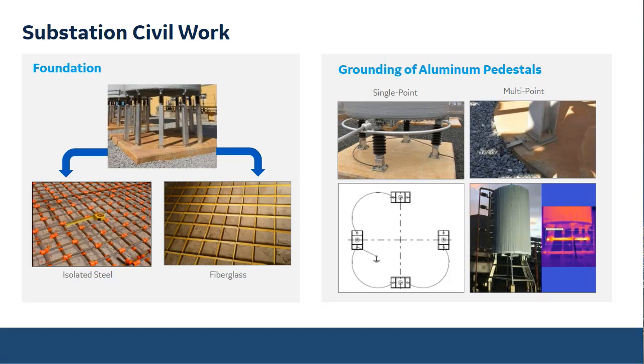We can see a lighter yellowish color, meaning that there was current flowing through that part. The design of the pedestal was not correct, and that caused a hot spot for that particular application. So the right way would be to cut a piece of that, open the loop to avoid current circulating through it. There are several ways to do the same thing, and we can provide the recommendations to you.